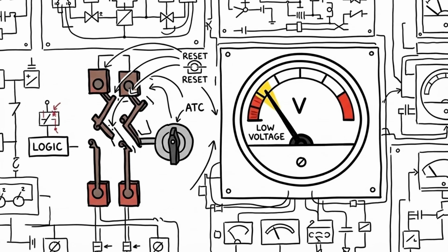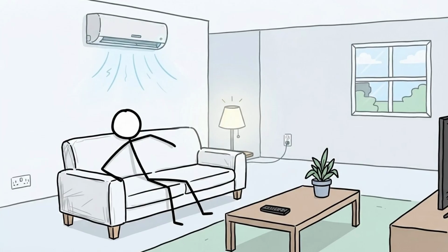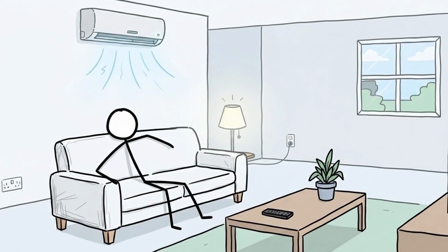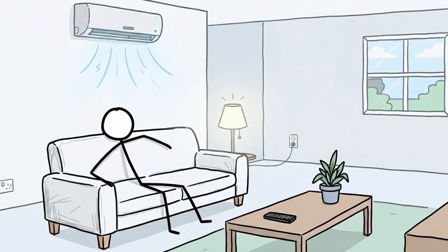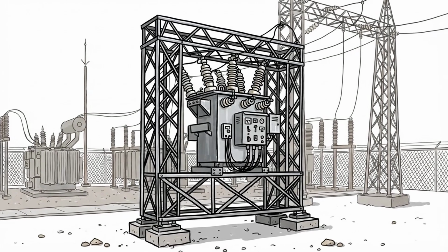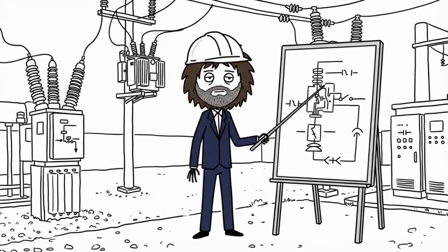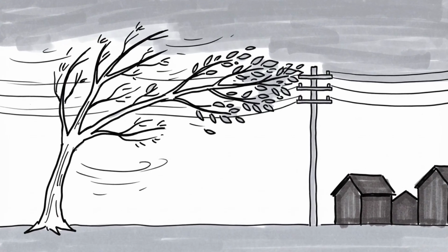The substation also houses automated voltage regulators, which constantly adjust the output up or down by switching internal transformer taps to make sure the voltage stays rock steady, even when millions of people turn on their air conditioners at 5 o'clock on a scorching summer evening.